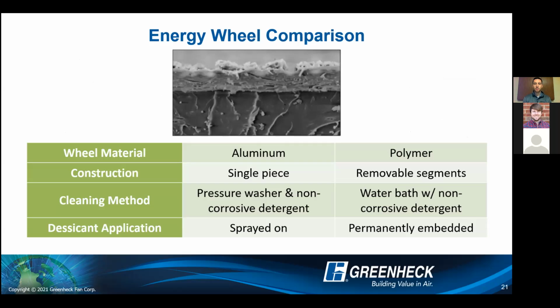And then for some more comparisons with the energy wheel, the aluminum wheel construction, it's a single piece. So what's nice about those polymer wheels is you get those removable segments. So from a maintenance standpoint or from a cleaning standpoint, a little easier to pull out. It's going to be lighter weight again because of that thickness. But cleaning wise, you can still pull out that aluminum wheel, pressure wash it, get some non-corrosive detergent, wipe it down or rub it off. And then with the polymer wheels, you take out those segments and give it a little water bath with some non-corrosive detergent like Dawn Dish Soap or 409 Fantastik. Give it a little soak time, rinse it off with a low pressure hose. Once it dries out a little bit, you put that back into the unit, and then it's all good to go, all clean. What you have to be careful of throughout this cleaning process is that desiccant application.